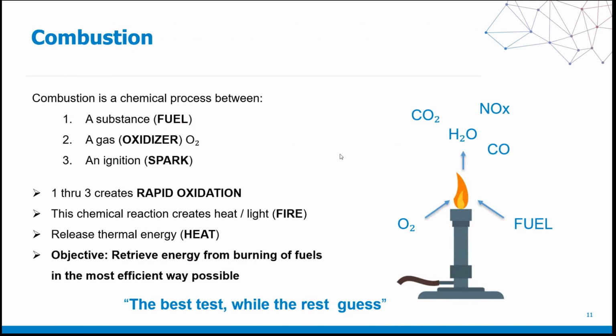Combustion. Before we go over what combustion is, I want you to think about it from this paradigm. I want you to view combustion as you view your annual physical at your doctor. When you go to your annual physical, you're having your height checked, your weight checked, your blood pressure, they're doing other diagnostic checks, blood and the like, and they're trying to ascertain the state of your health. Now, they're not doing it just by looking at you. You don't just come in the office and they say, oh, you look like you put on a few pounds, just do this and that, pay your copay and be off, you're good. They're not doing that. They're actually doing diagnostic checking, checking the internal workings of your body to make sure that you're functioning properly, and they're comparing those to the benchmarks of health based on your age and those other factors. So when we do a combustion analysis, that's exactly what we're doing. We are essentially checking the state and welfare or the health of that appliance, whether it's a furnace, boiler, or water heater.